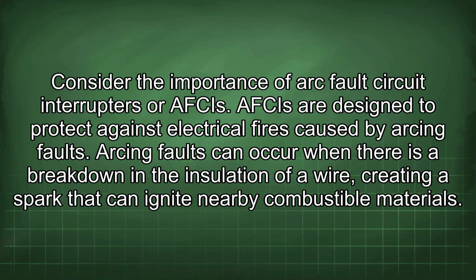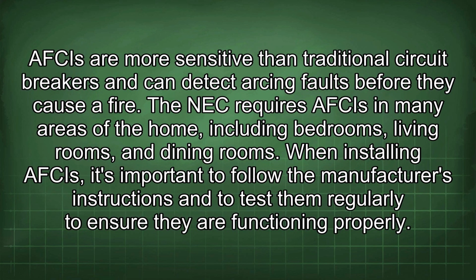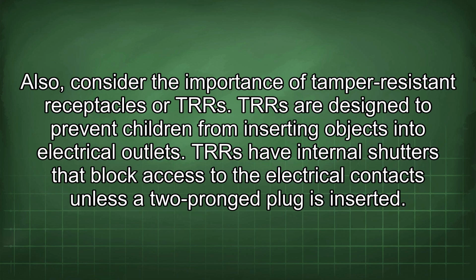Consider the importance of arc fault circuit interrupters, or AFCIs. AFCIs are designed to protect against electrical fires caused by arcing faults. Arcing faults can occur when there is a breakdown in the insulation of a wire, creating a spark that can ignite nearby combustible materials. AFCIs are more sensitive than traditional circuit breakers and can detect arcing faults before they cause a fire. The NEC requires AFCIs in many areas of the home, including bedrooms, living rooms, and dining rooms. When installing AFCIs, it's important to follow the manufacturer's instructions and to test them regularly to ensure they are functioning properly.